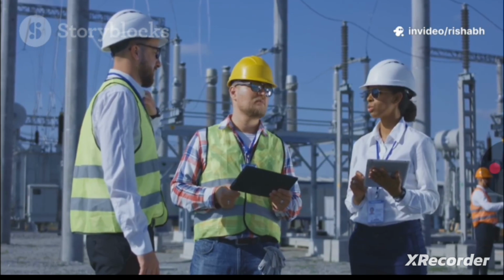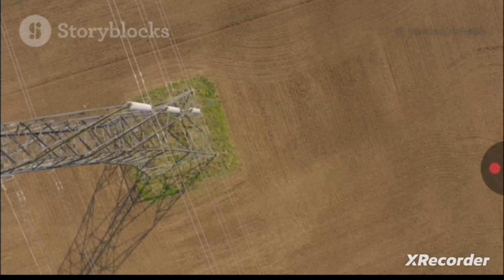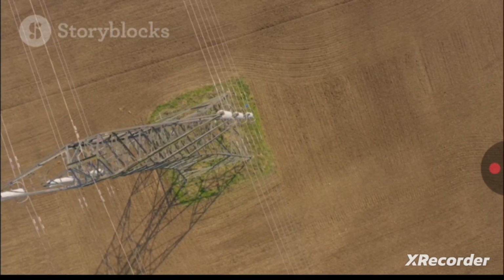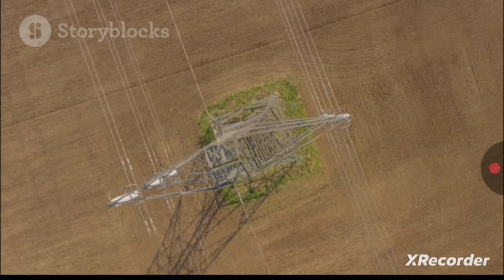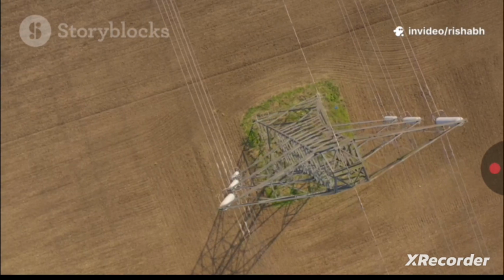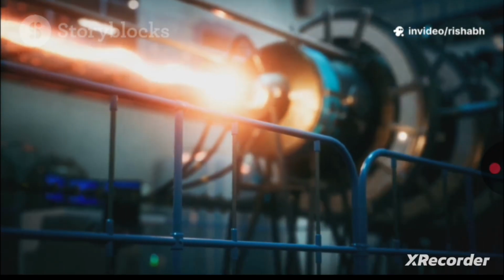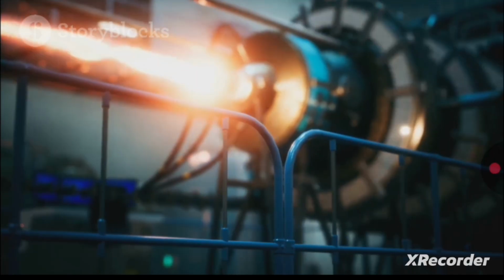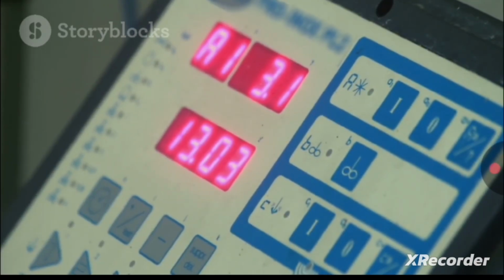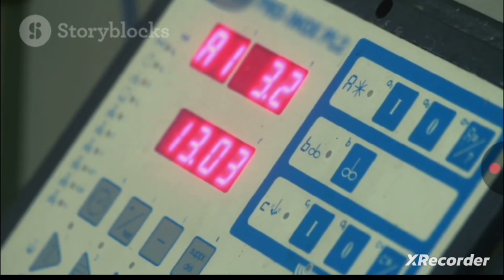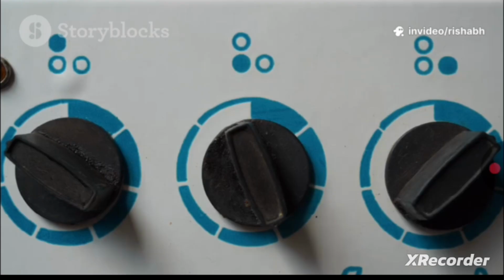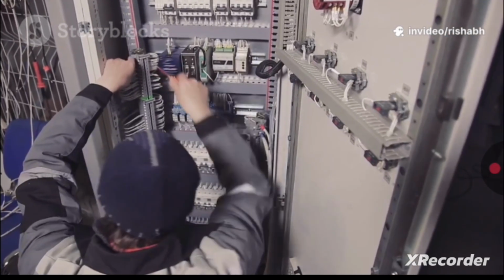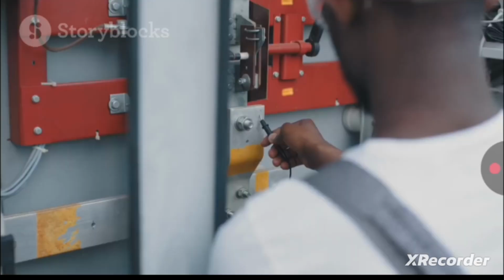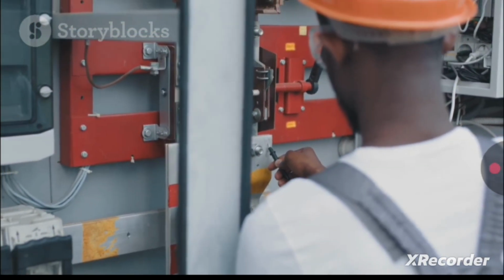There are several real-world scenarios where these relays are essential. One common cause is a large load being suddenly disconnected from the grid, which can cause the system voltage to rise. This is called the Ferranti effect on long lines. Another is during the startup or shutdown of a generator connected to the transformer. As the generator spins up, its frequency is low, creating a high voltage over frequency ratio. A similar situation occurs during shutdown. Operator error, such as selecting the wrong tap on a transformer's tap changer, can also apply an incorrect voltage and lead to overfluxing. The voltage over frequency relay is designed to handle all these possibilities.